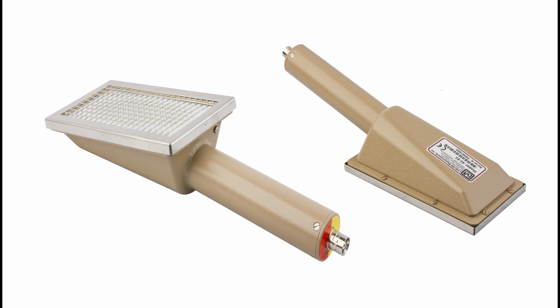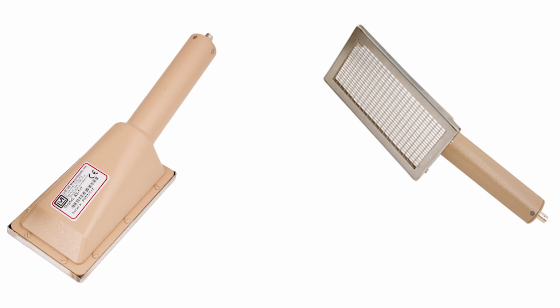This system typically comes equipped with a Model 43-93, the 100 square centimeter alpha beta detector. Since this is a scintillation type detector, there's no gas flow system required to operate this system. Other detectors are available, including the Model 43-147, the 200 square centimeter alpha beta scintillator.